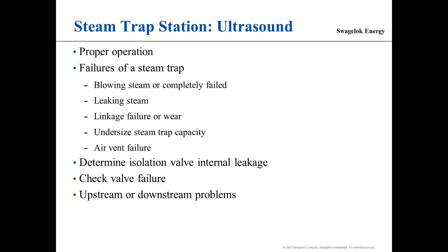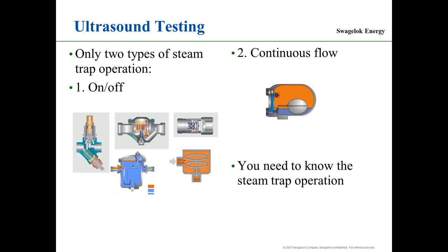The other thing is to determine isolation valve internal leakage. It also gives me the ability to check for check valve failure. In a percentage of cases, you'll find with ultrasound that it's not the steam trap making the sound, it's the check valve. So you'll be able to determine check valve problems. And you'll also determine upstream and downstream problems, which I'll get into when I talk about the testing points of a steam trap. So there's your list of things you can test.